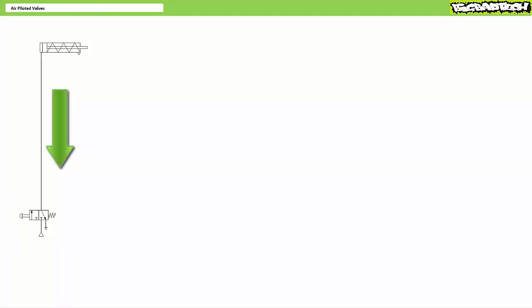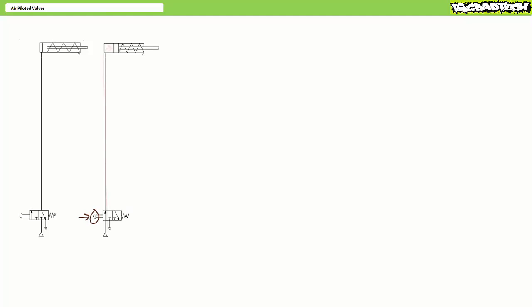Let's say for safety reasons the operator station needs to be some distance from the actuator. In the deactivated state, the cap end is exhausted to atmosphere and the cylinder is retracted by the spring in the rod end. When an operator presses the push button, the valve moves into a position such that pressurized flow is routed to the cap end. Given the long length of line between the pneumatic source directional control valve and actuator, one might expect significant pressure losses in the line such that the single acting cylinder extends weakly and slowly, if at all.